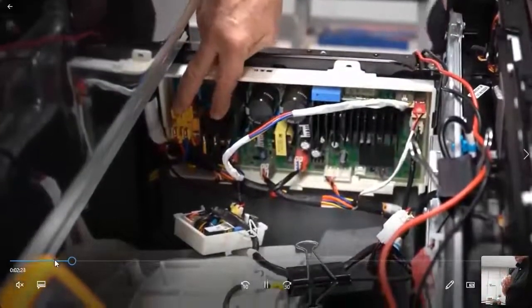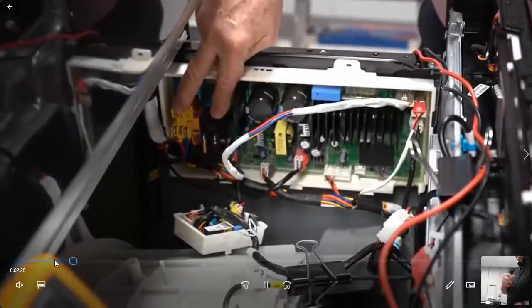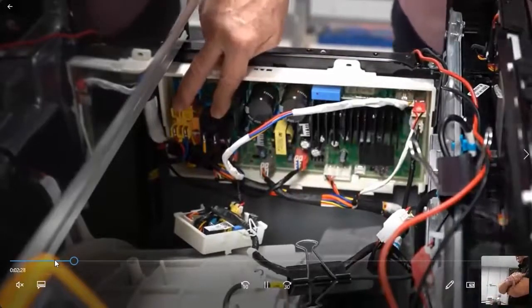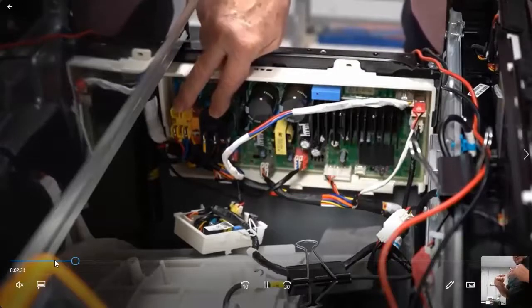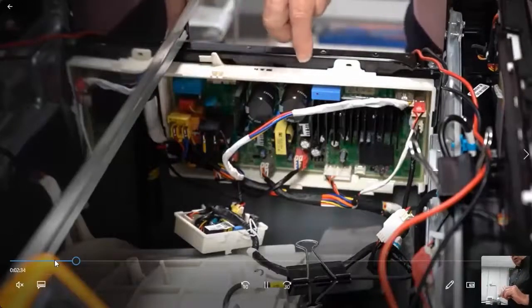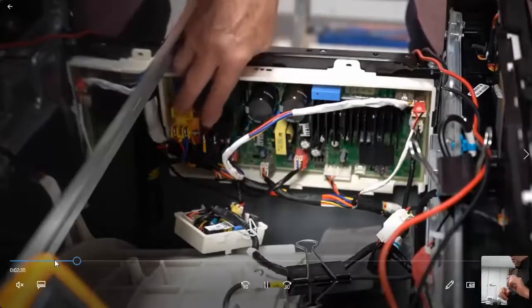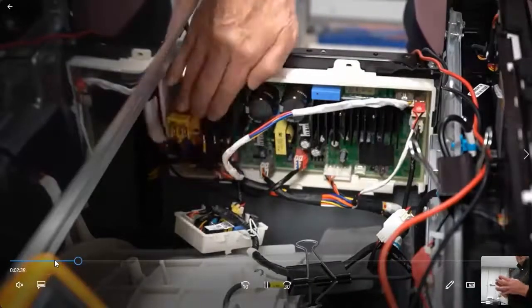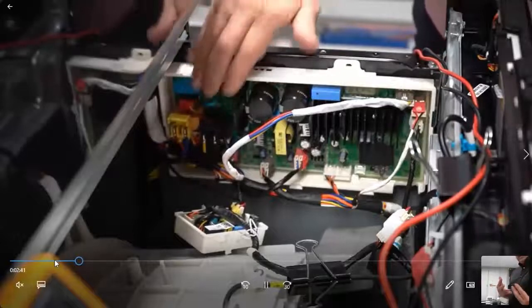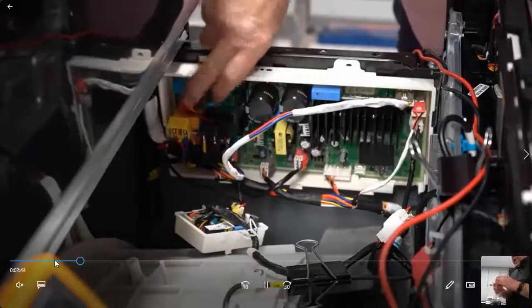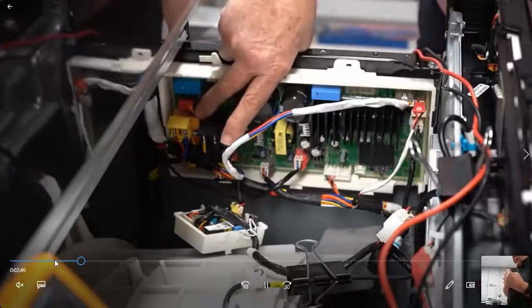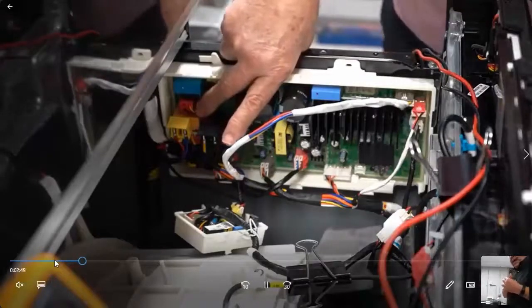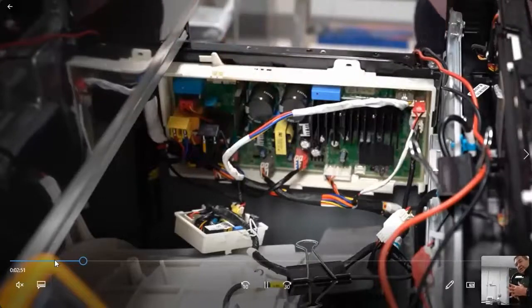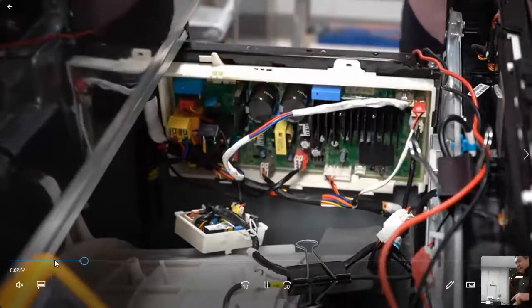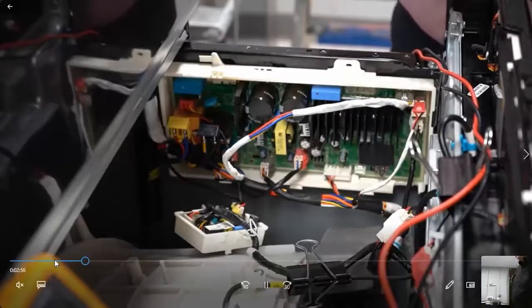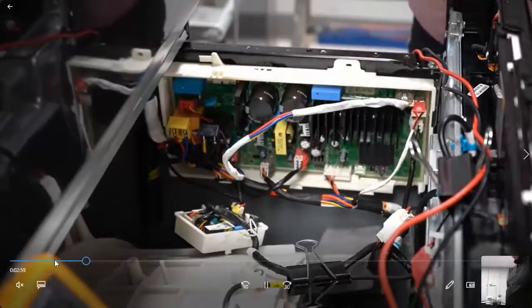One thing I'll caution you on: if you pull that connector away from the board and want to do a resistance check, please do not insert those probes from the part that connects to the main board. Those are very tiny connections, and you're going to damage them. We've seen situations where units came back to us because they couldn't be repaired, and when we pulled off that connection, you could see where the needle probe was forced inside there, causing a poor connection. So only do your connections from where the wire is, to prevent damage.